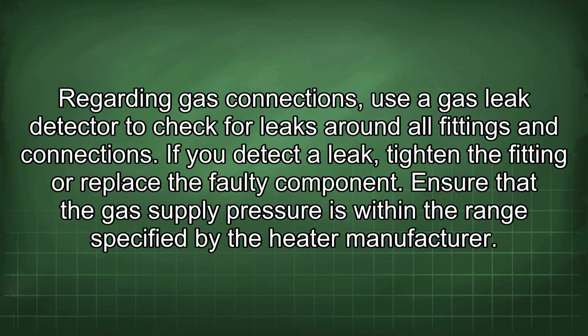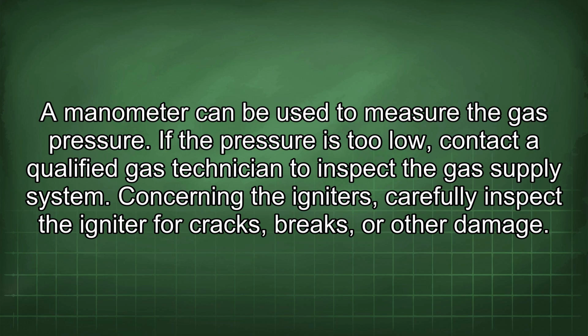Regarding gas connections, use a gas leak detector to check for leaks around all fittings and connections. If you detect a leak, tighten the fitting or replace the faulty component. Ensure that the gas supply pressure is within the range specified by the heater manufacturer. A manometer can be used to measure the gas pressure. If the pressure is too low, contact a qualified gas technician to inspect the gas supply system.